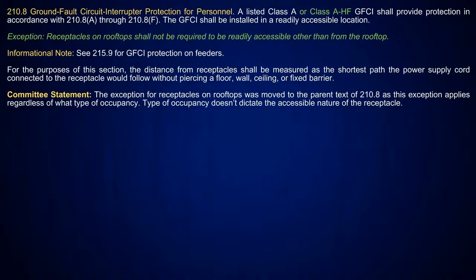Now, at the first of 210.8, they added Class A HF GFCI. They did have that, but the real change is the exception: receptacles on rooftops shall not be required to be readily accessible other than from the rooftop. So what they did is move this into the parent text of 210.8 as an exception, meaning it applies regardless of what type of occupancy it is.